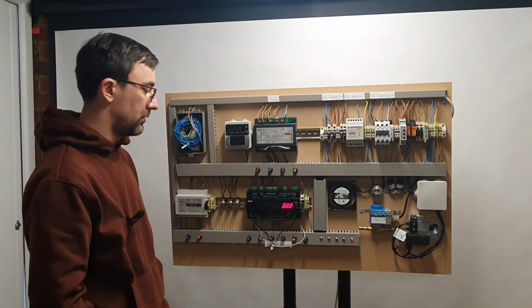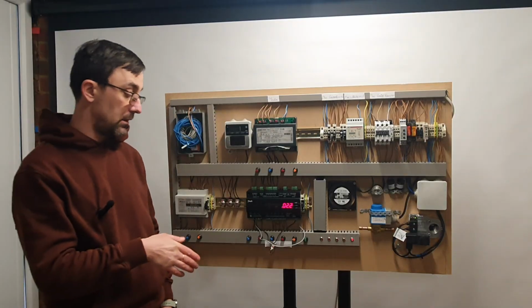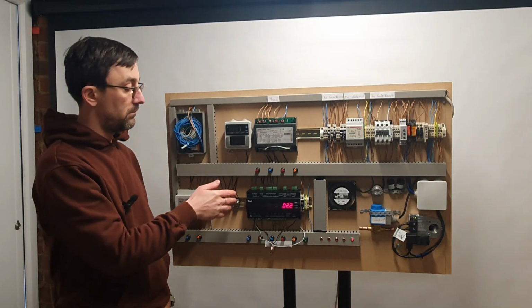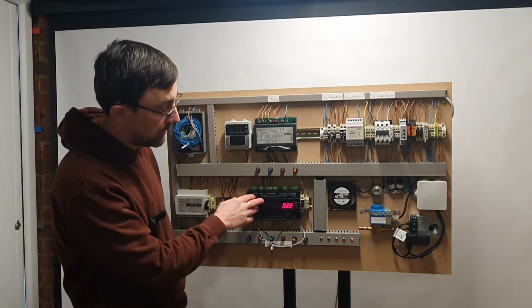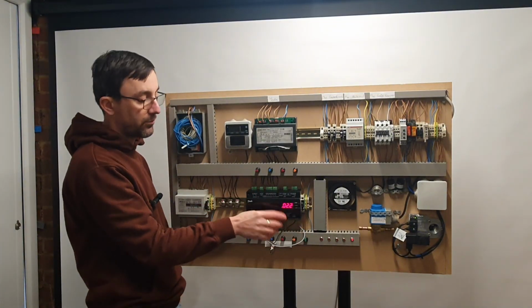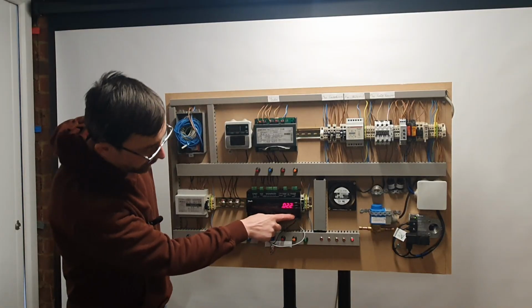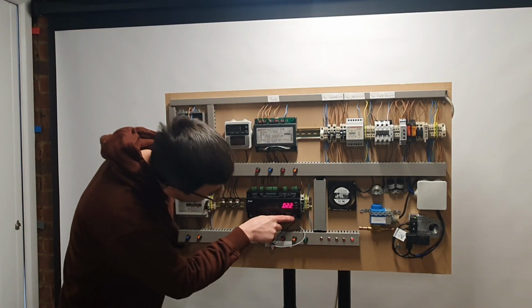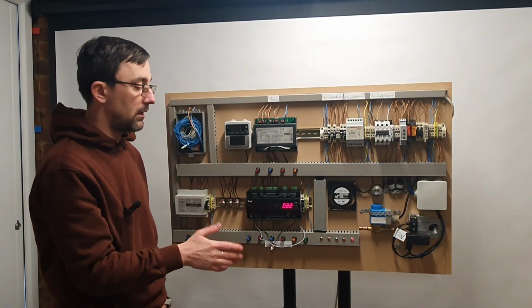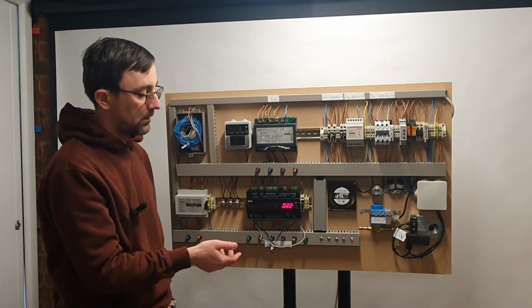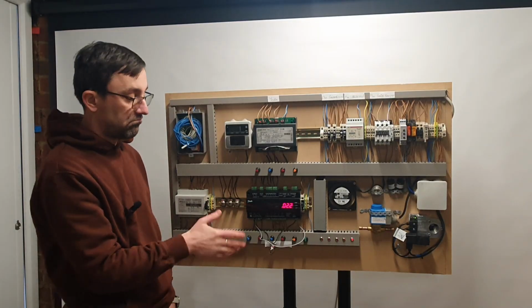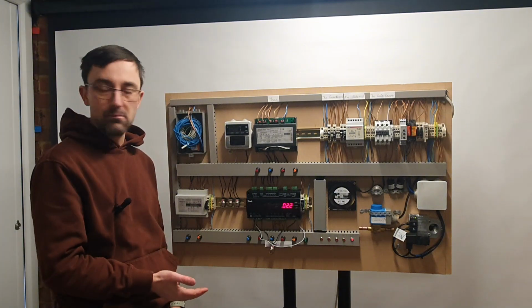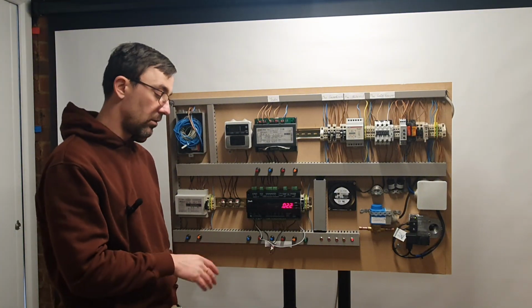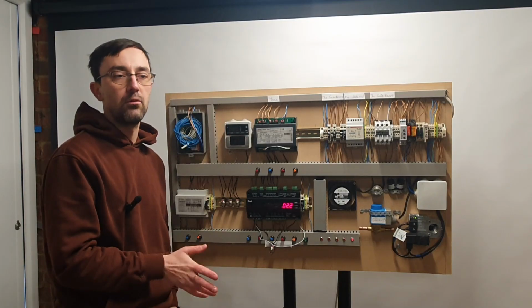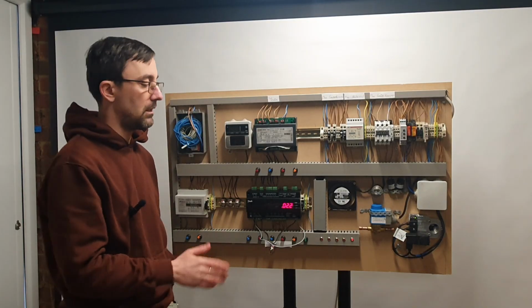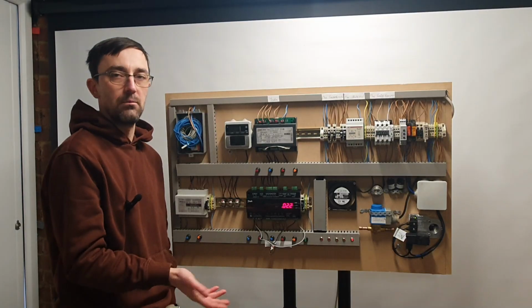Okay, so I did something wrong. It's because the wiring diagram in the controller manual that I have doesn't tell me exactly how to wire digital input number 3. It just says 230 volts, and it gives you 2 connections. But it doesn't say live in, live out. It doesn't say live and neutral. That's all it says. So I consulted the manual, tried to find a bit more information. All it says is high voltage digital input, nothing else. That basically means 230 volts.